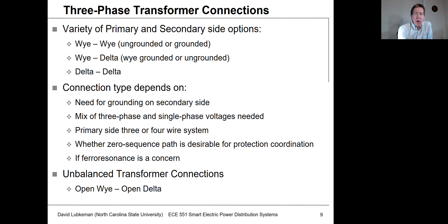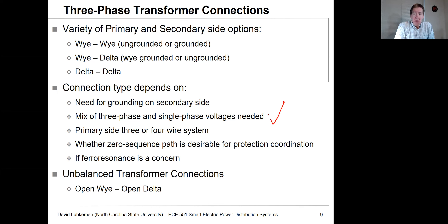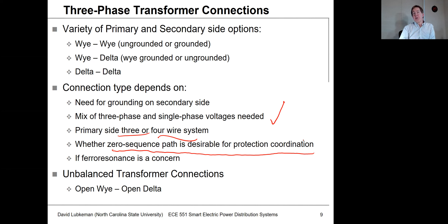The connection type you want to use in the field depends on your grounding needs — if you need to ground on the secondary side, you'd use some sort of grounded-Y connection. It also depends on what types of voltages you need, whether the primary has a four-wire or three-wire supply, and importantly, what you want for the zero-sequence path: what do you want to happen with ground currents if there's a fault on the primary or secondary side? This overlaps with protection practices.